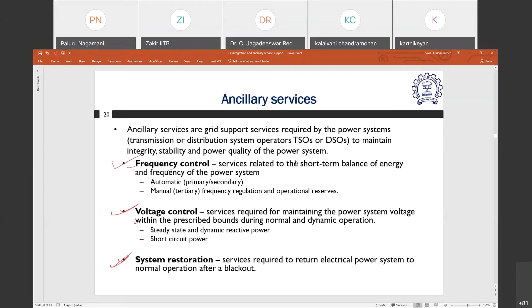There are of course economic aspects, where you have to minimize the cost of grid operation. That's fine, but technically all you have to think about is generation-load balance, both active and reactive power. For frequency control you need frequency reserves. For voltage control you need reactive power reserves. System restoration or black start service is the third ancillary service, which is again a combination of active and reactive power support. Because if there's a blackout in the grid, you have to start the grid back again. You need some generators to maintain the voltage first, and then the other generators can come in. So broadly you can divide grid ancillary services into these three categories.